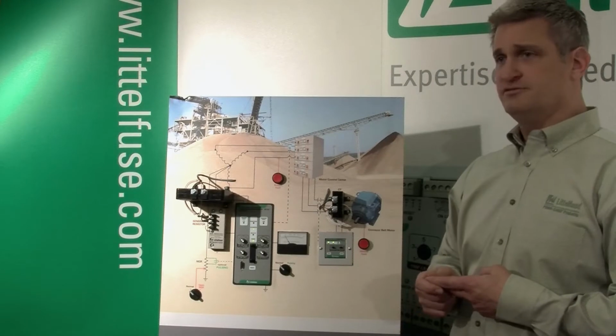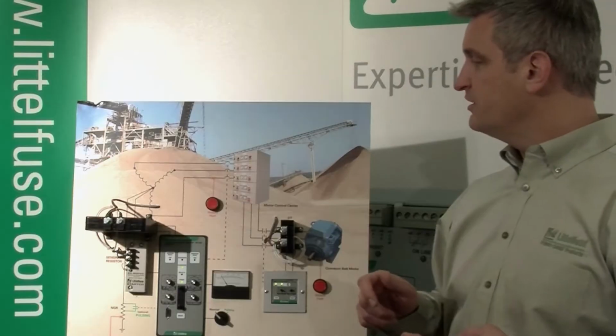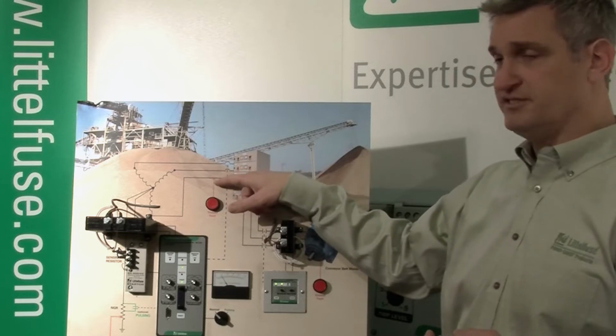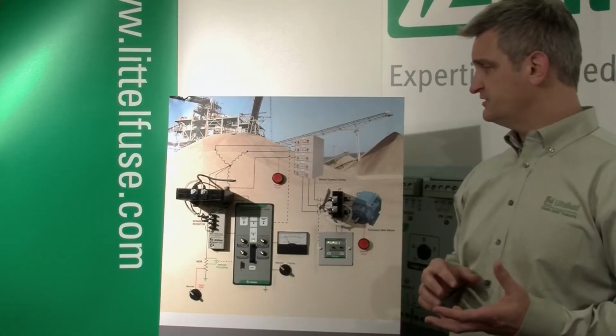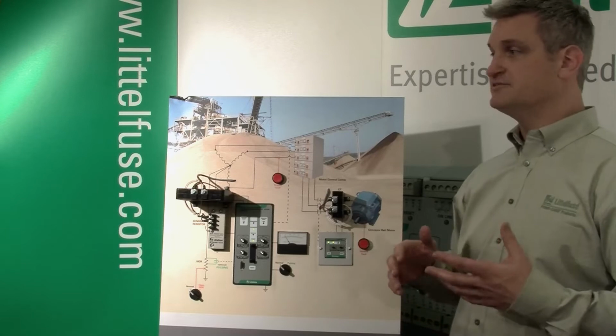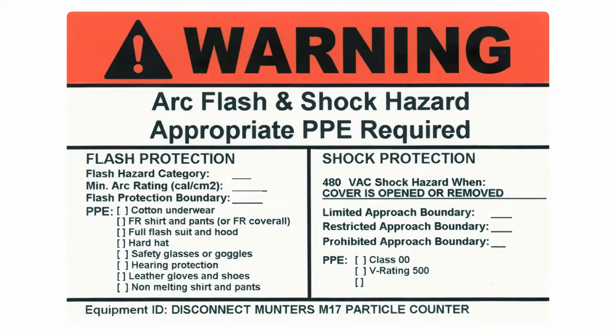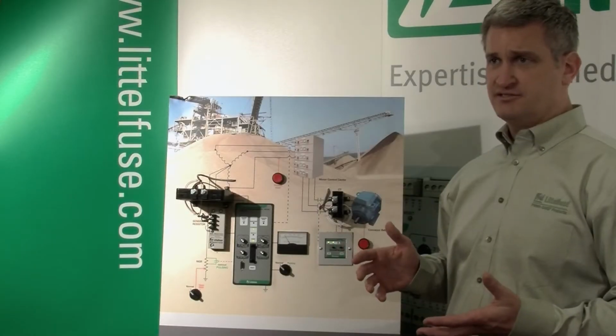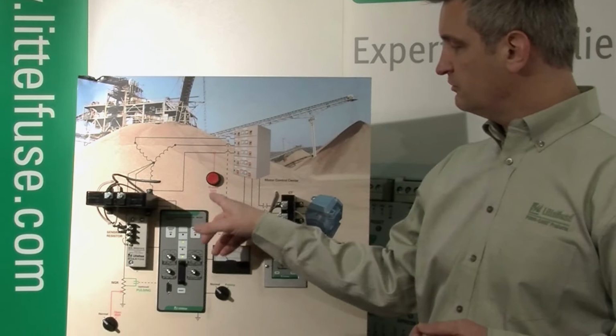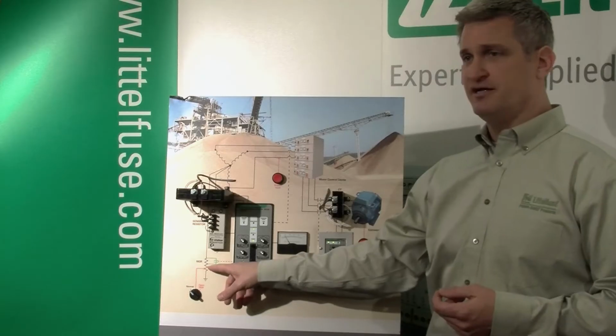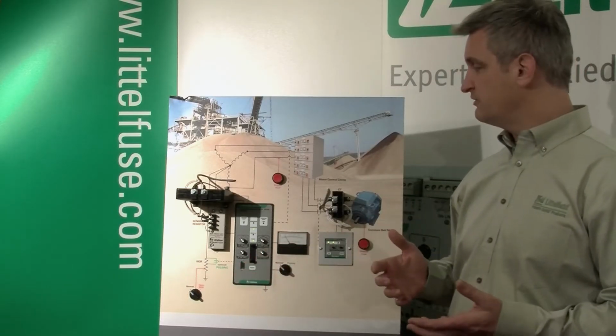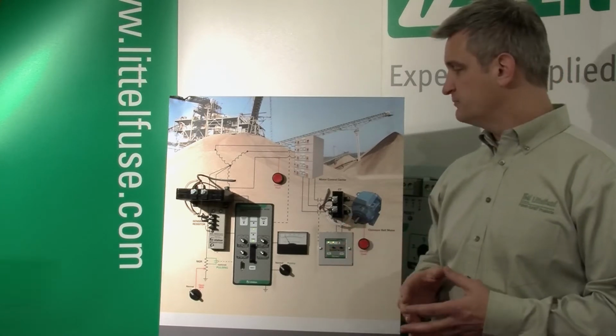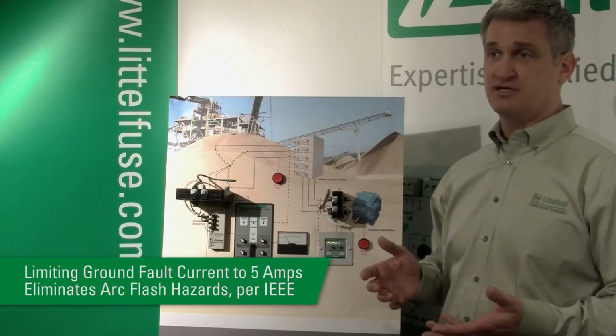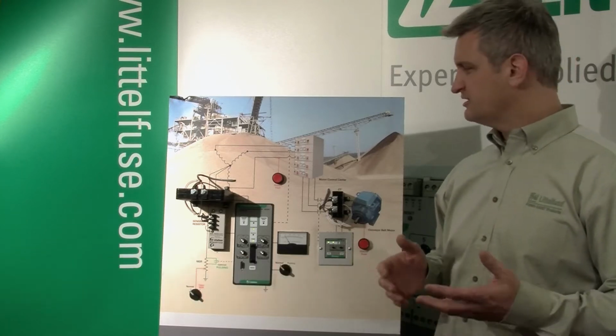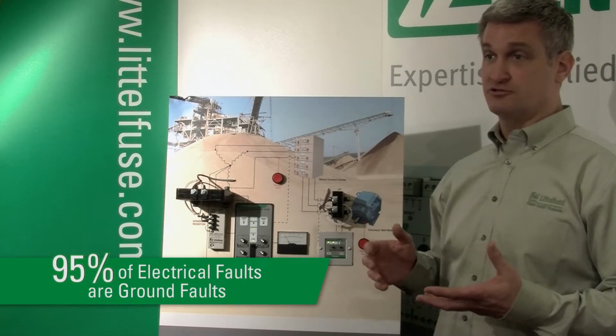There are two main reasons for using resistance grounding systems. One is if you have a ground fault in the system, shown here on C phase to ground. In a different type of system grounding, a solid grounded system, the ground fault current will be tens of thousands of amps. That leads to the arcs and the sparks and the explosions that you always hear about, the arc flash hazards. But that doesn't happen with resistance grounded systems. The reason is that when the ground fault goes to ground, it's limited by the resistance. So it physically limits that ground fault current to a couple of amps. And IEEE says if you limit the ground fault current to 5 amps or less, there are no arc flash hazards. And some sources say up to 95% of electrical faults are ground faults.